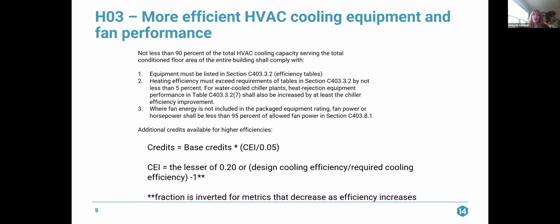Where fan energy is not included in the packaged equipment rating, fan power or horsepower shall be less than 95% of allowed fan power in section C403.8.1. So basically what we're looking for there is if the unit that we are specifying does not include the energy, or the cooling efficiency doesn't include the energy of the fan, then we need to make sure that it is also at least 5% better than the allowable fan power.